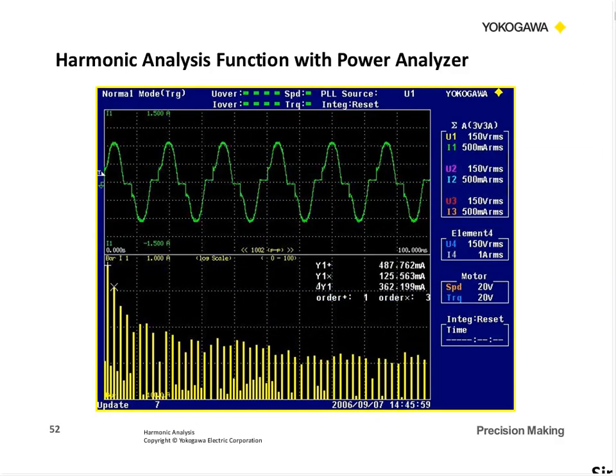So here's the analysis on the same waveform. This is done in the power analyzer, where we use a phase lock loop to get the fundamental, and we get a true integer number of waveforms. I'm not sure where this starts, but it determines it all internally in the DSPs, and so we have a true integer number of cycles that we do the math calculation on. Now we've got a clean waveform. We can measure all these amplitudes, and you can see some of the odd and even harmonics, all the way across, very clear.